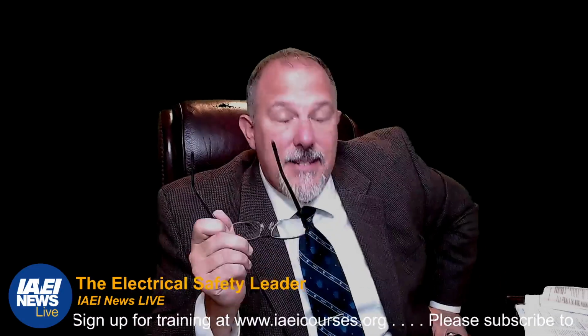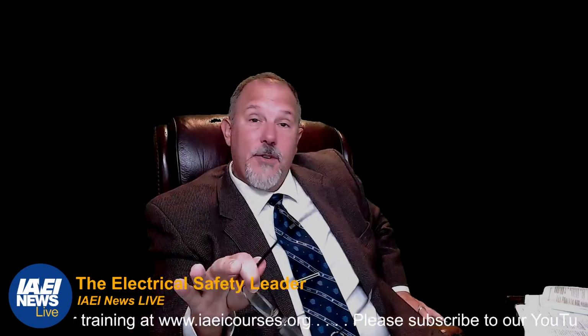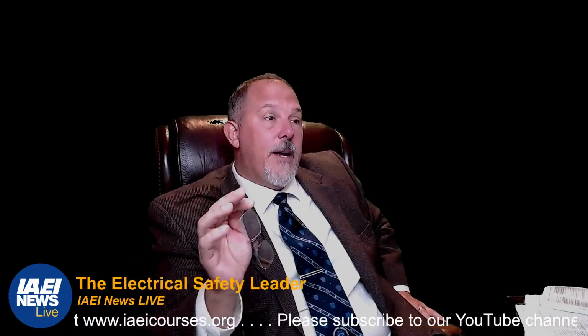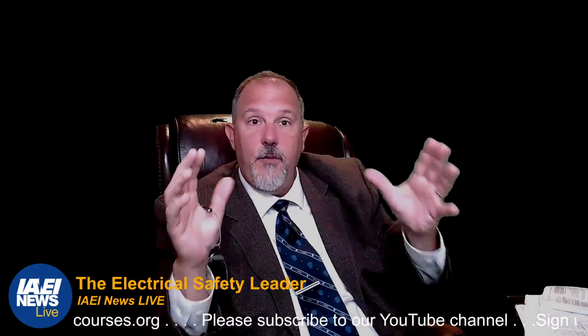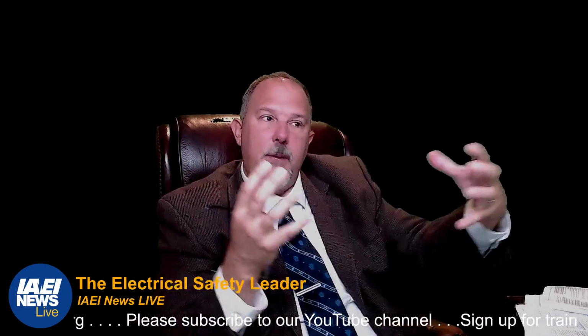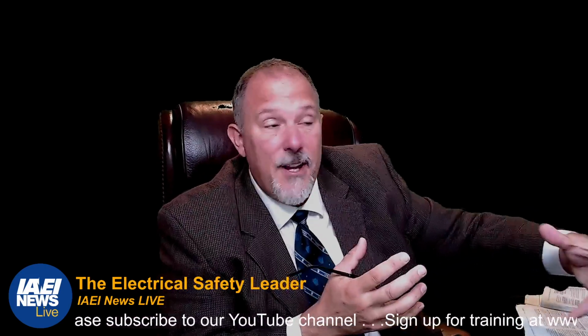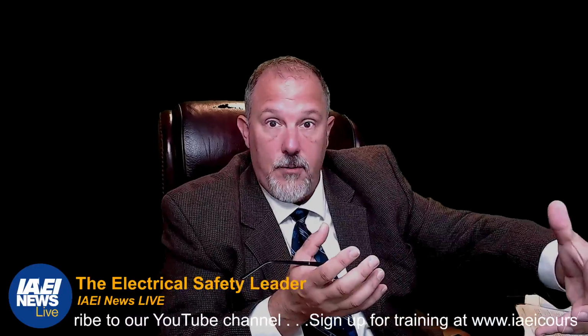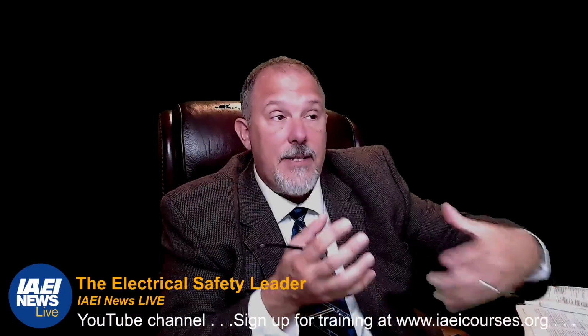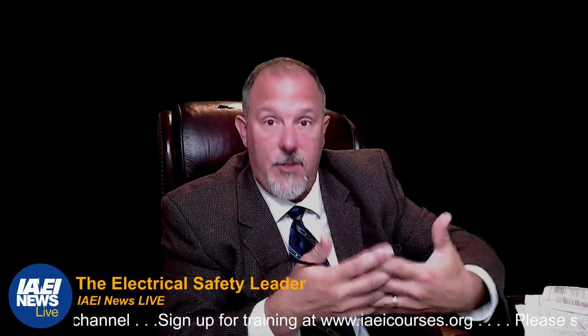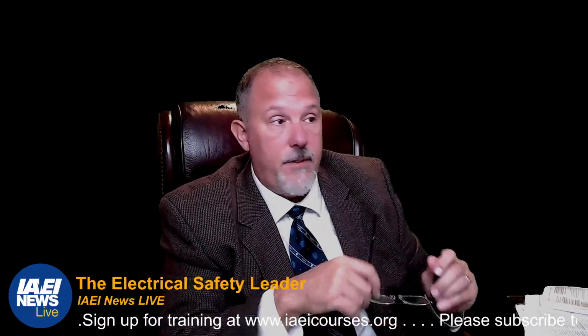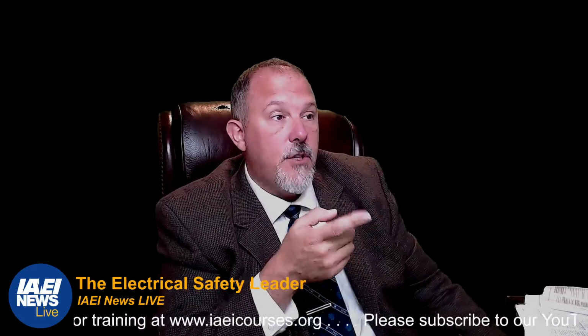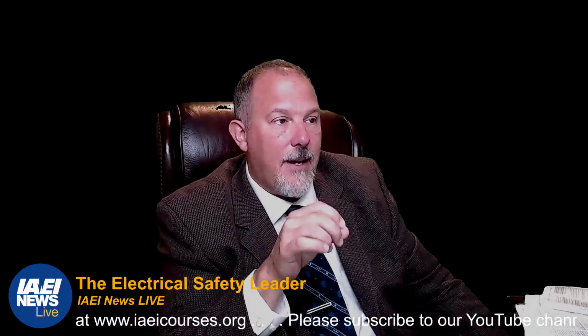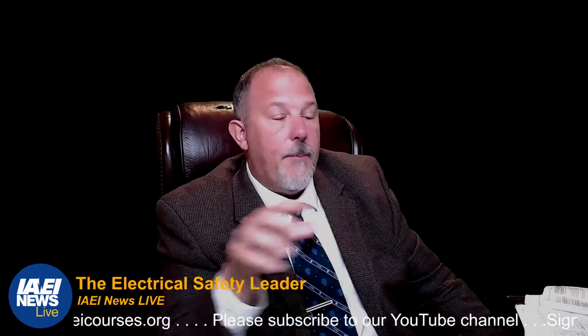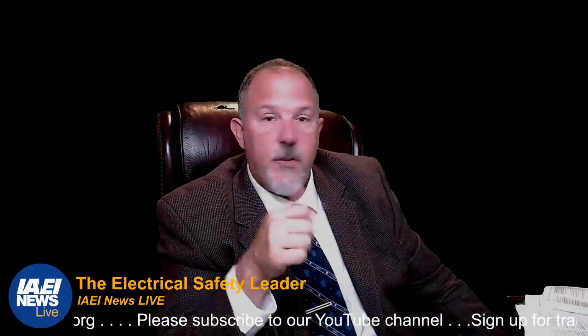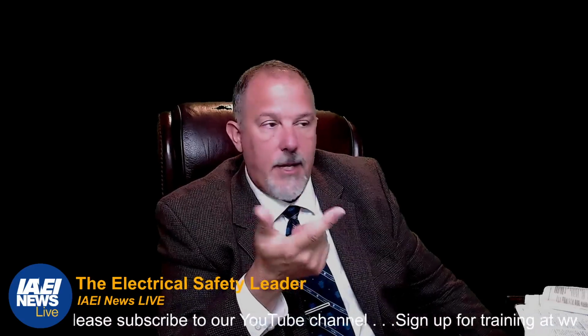Inspect the external physical condition. Remember, I just told you that. Inspect the anchoring and grounding. So if you see maybe the enclosure's doing great, but what you mounted it to isn't, the integrity of the structure that you're mounted to makes a difference. Verify the breakers and fuses and overload elements are the right sizes and types based upon the studies, which could be a short circuit study, coordination study, all that jazz.